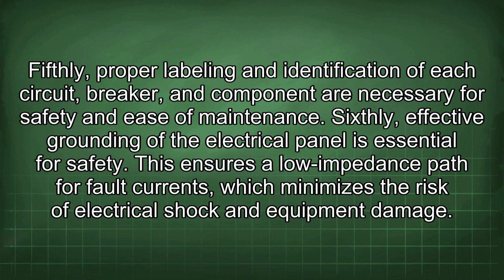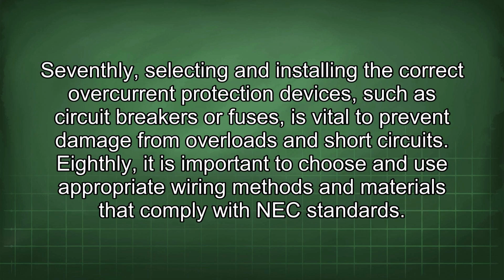Fifthly, proper labeling and identification of each circuit, breaker, and component are necessary for safety and ease of maintenance. Sixthly, effective grounding of the electrical panel is essential for safety. This ensures a low impedance path for fault currents, which minimizes the risk of electrical shock and equipment damage. Seventhly, selecting and installing the correct overcurrent protection devices, such as circuit breakers or fuses, is vital to prevent damage from overloads and short circuits.